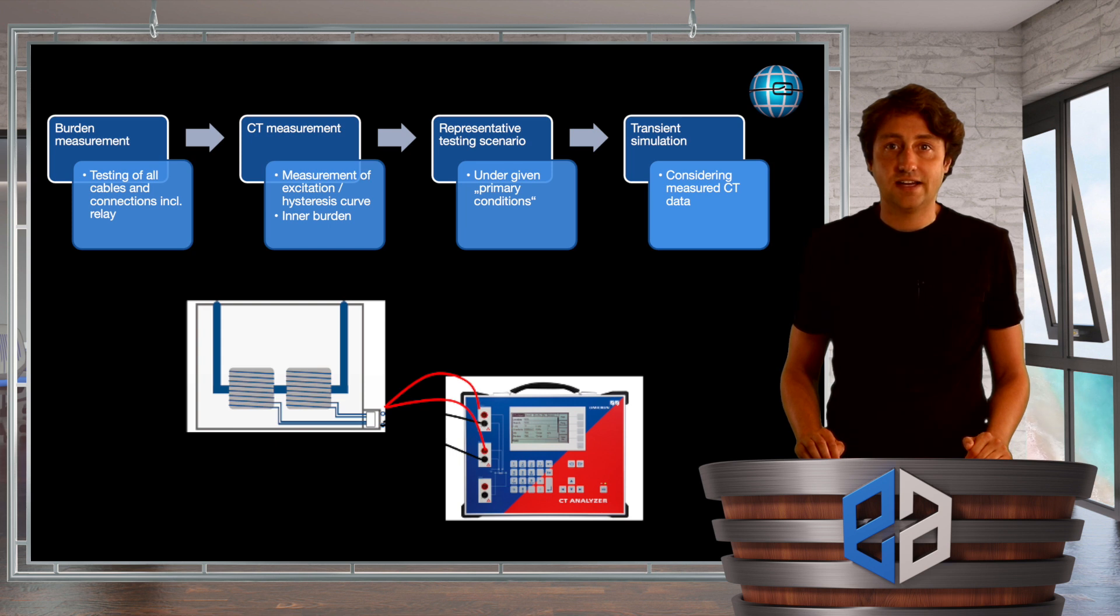Then we define a representative testing scenario under certain given primary conditions. And then we put this data into a software for transient simulation that is considering our measured CT data. Like this we can simulate how our CT will perform in certain conditions and thus get a picture how prone a certain setup is to the problem of remanence.